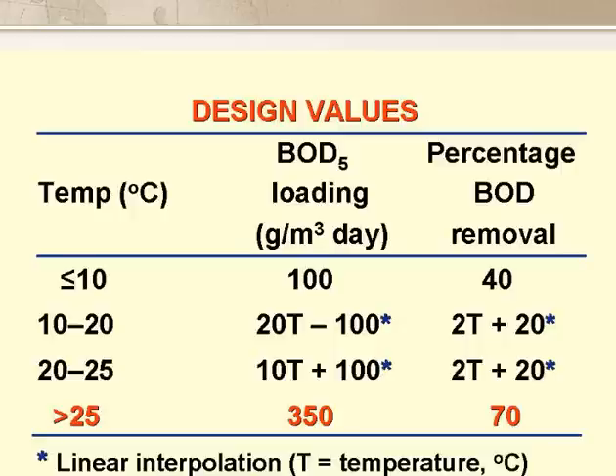The BOD removals that we assume in our design are 40% at 10 degrees and below, 50% at 15 degrees, 60% at 20 degrees, and 70% at 25 degrees, again with linear interpolation in between.